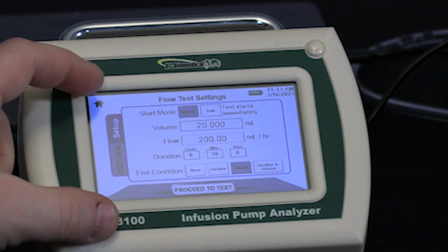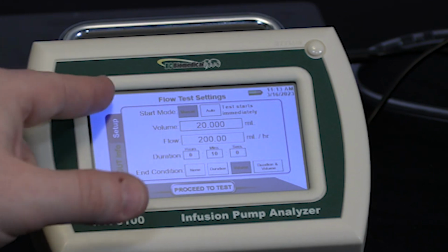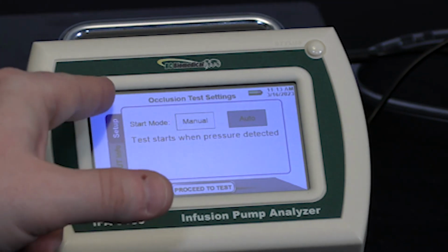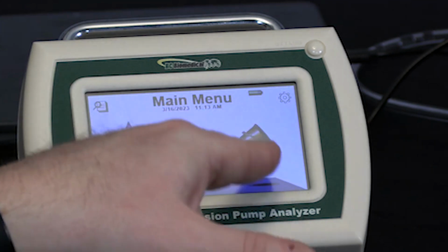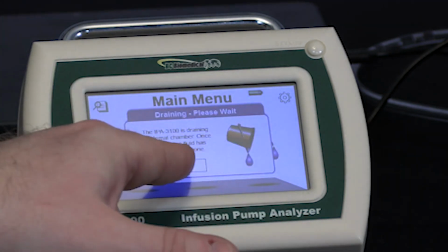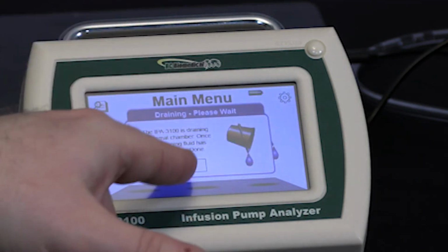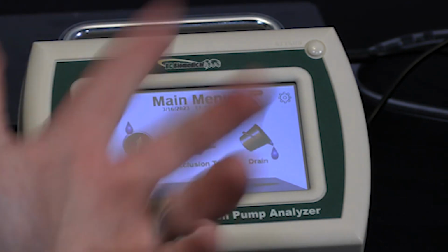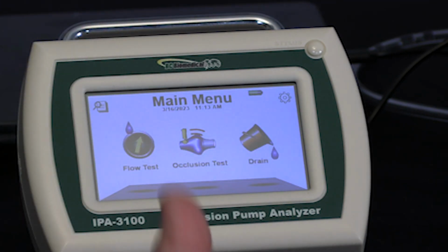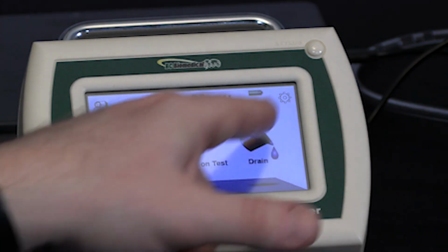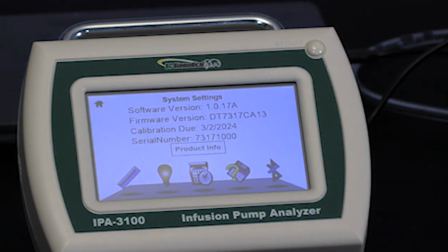For navigation, we just select which test we want to perform, either flow test or occlusion tests. We can drain the module just by pressing the drain button. It will automatically clear any fluid, which is useful for when we need to ship the unit, where it might be exposed to freezing temperatures. We've got our settings right at the top.